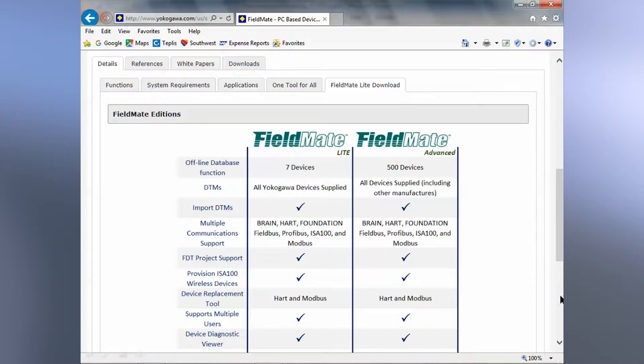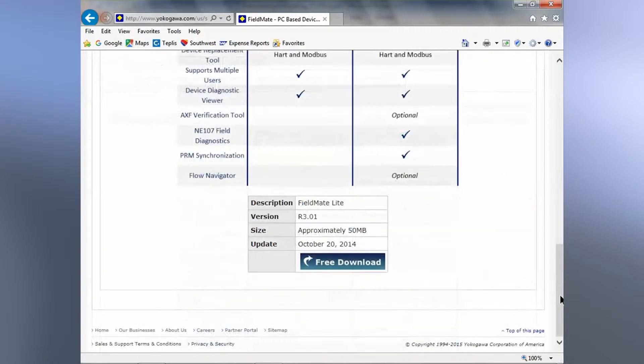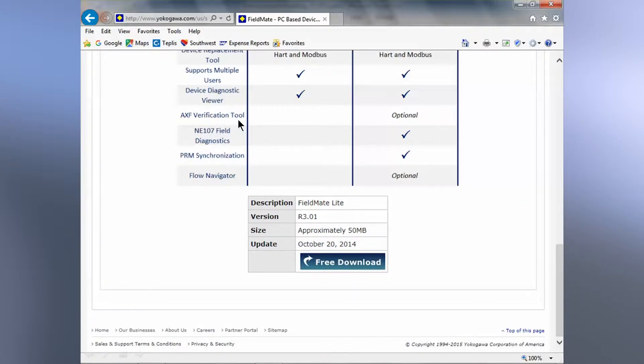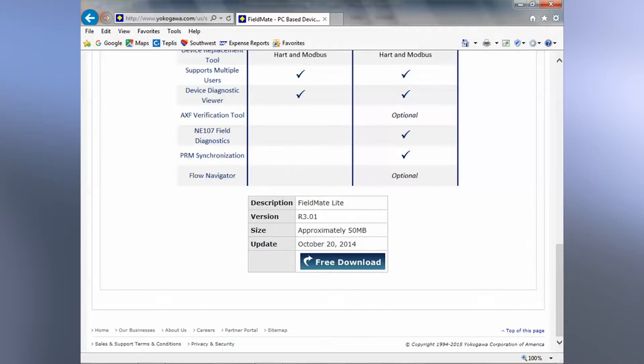If you scroll down a little bit further, you'll see a couple other differences. The AXF verification tool is a second software program that can be purchased when you want to confirm the accuracy of a Yokogawa AXF mag meter rather than having it pulled from the process and shipped back to the factory. This can save a lot of time and money.